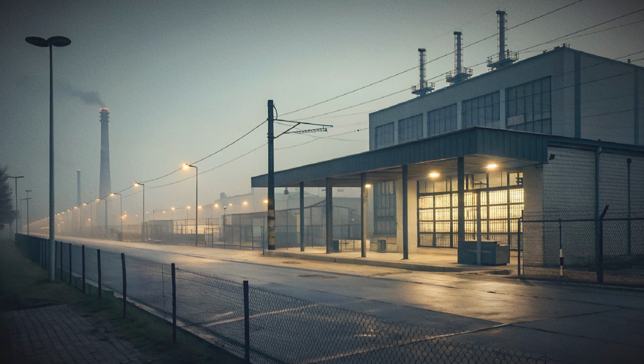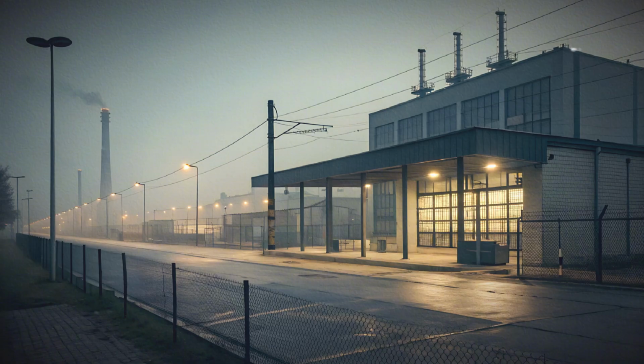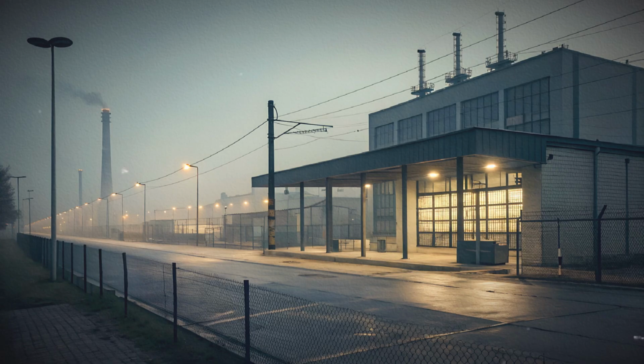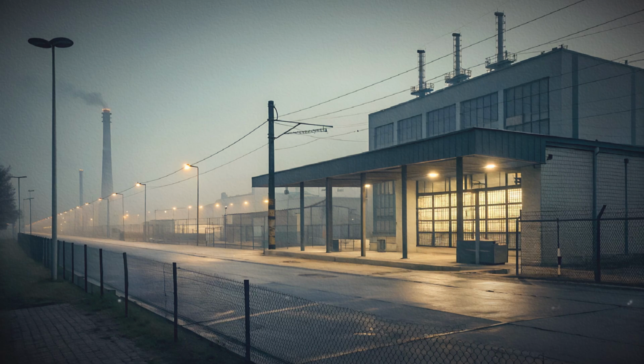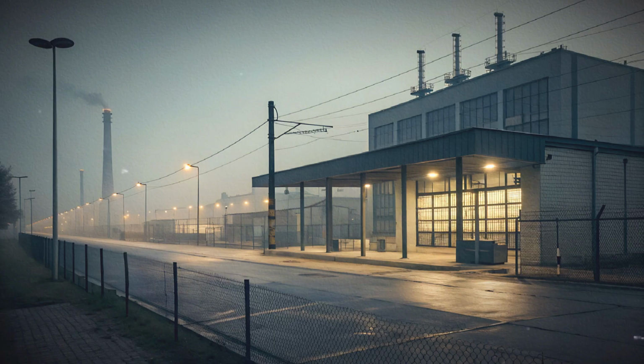Condition monitoring and predictive maintenance have become central to long-term reliability. Sensors measure temperature, vibration, oil quality, and electrical characteristics. Data is collected continuously or at regular intervals. Analytics identify trends that indicate deterioration. Predictive models estimate remaining useful life for individual components. Maintenance can then be scheduled before failure occurs. This reduces unplanned outages and concentrates work when it is least disruptive.